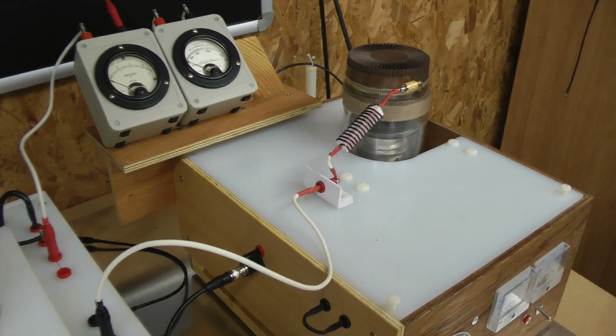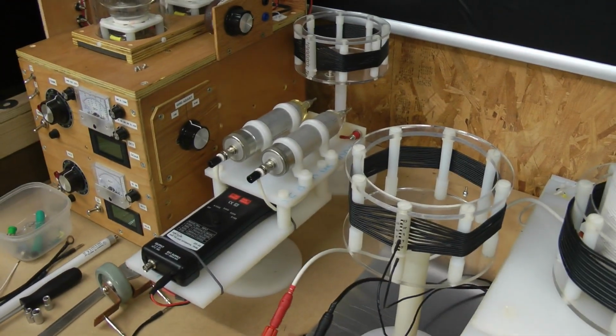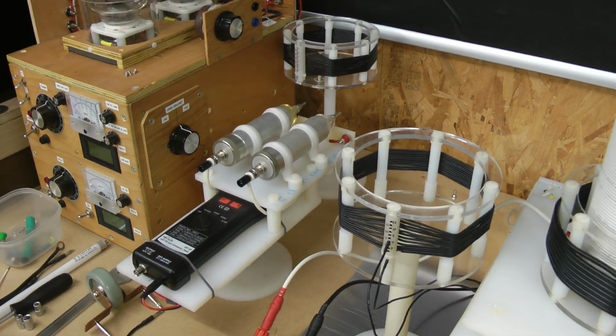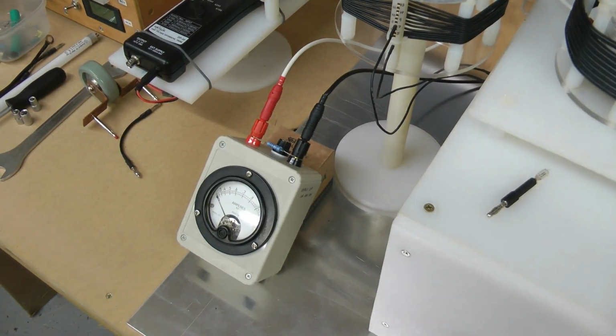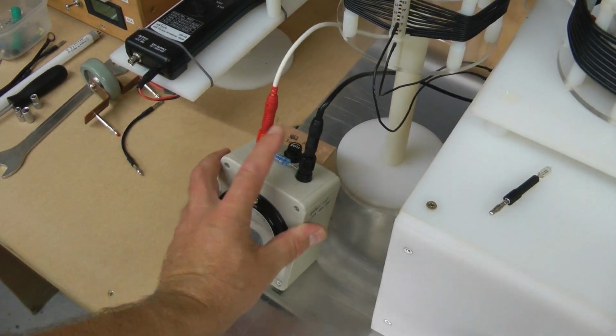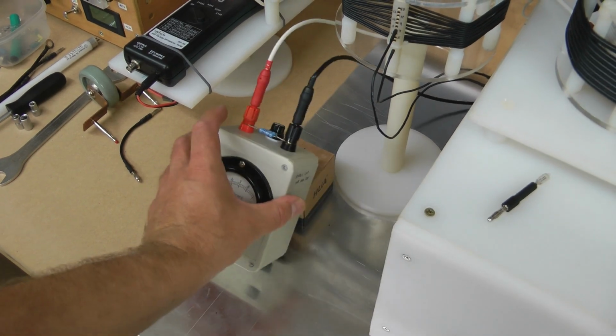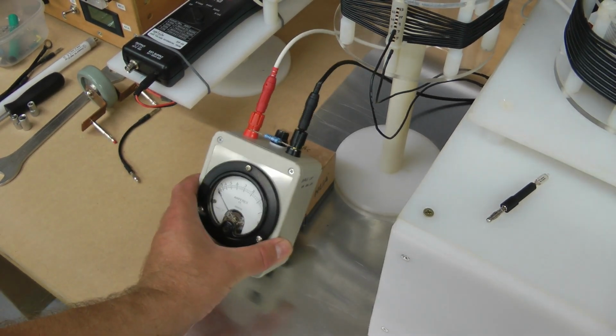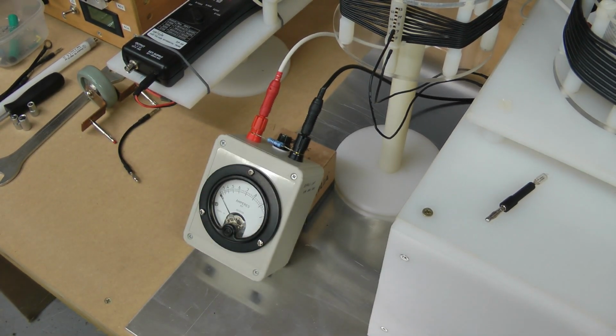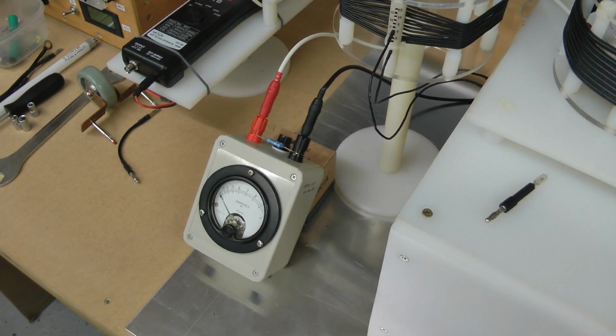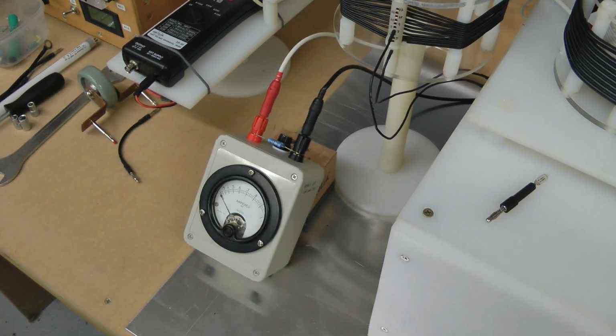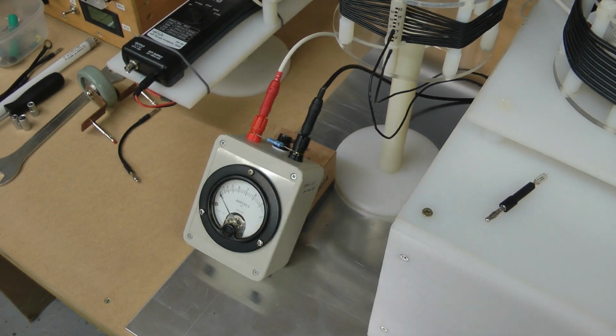These have got bypass capacitors, so you can see from this one here, if I bring it down and put it up on its end, there is a fuse there. I like to put the fuse at twice the meter capacity. These meters are quite strong, but the fuse will blow and preserve the meter, and I would rather that happen than lose the meter.